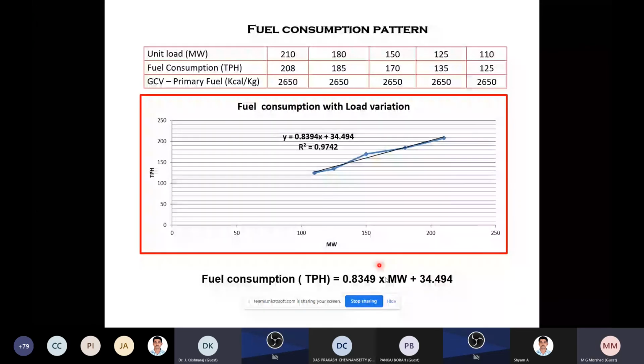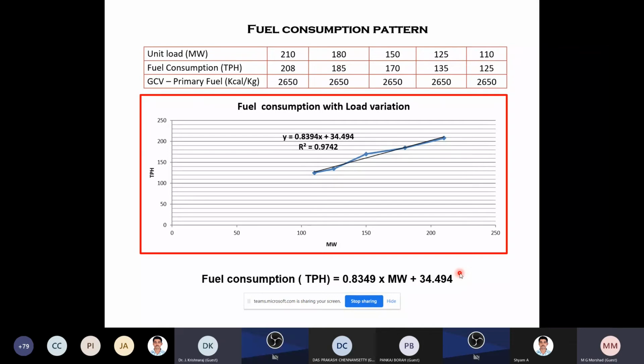In this graph, you will see the 35 ton per hour of lignite is fixed, whatever the load is. After that, it depends on the megawatt into this factor. So after this 34 ton per hour, it will go higher. So this is the fuel consumption graph with the load variation. That is also one of the very good things. I have not seen it in any other energy audit report, but in our plant we have established it. We try to find out the minimum lignite consumption for the minimum load. That is one of the good parameters for studying the boiler conditions of any thermal power plant.